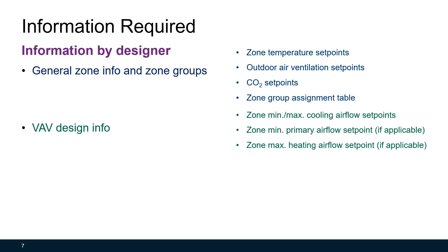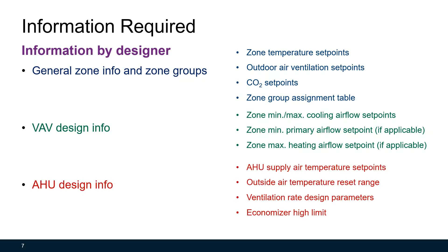You also need some VAV design information such as zone minimum and maximum cooling airflow set points, zone minimum primary airflow set points, and zone maximum heating airflow set points if applicable. For air handling unit design, you need AHU supply air temperature set points, outside air temperature reset range, ventilation rate design parameters, and economizer high limits.